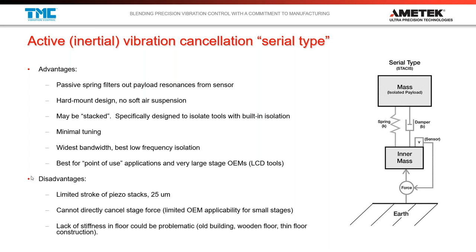Second question: in the case of stacking an active on a piezo active system, what is the typical maximum mass the piezo actuator can support? Most isolation systems are modular — isolators are designed for certain weight capacities, and as you want to increase the weight supported, you add more isolators. A STACIS isolator, which is the piezoelectric serial type system, has a maximum capacity of 4,500 pounds for one isolator. But if an instrument weighs 10,000, 20,000, or 40,000 pounds, you can add more isolators, since each isolator is a self-contained feedback control system.